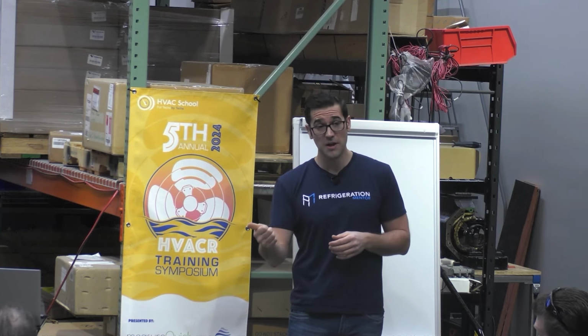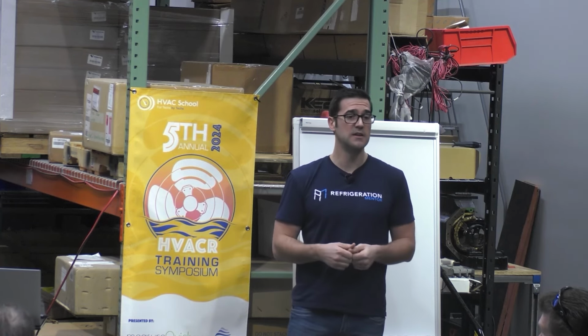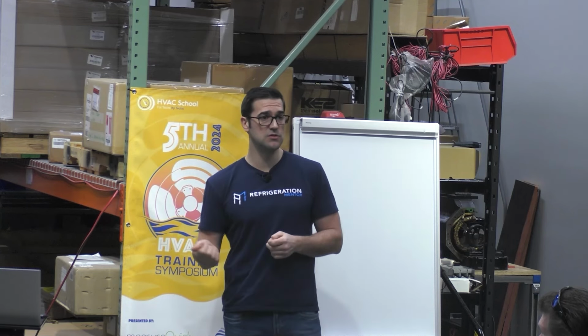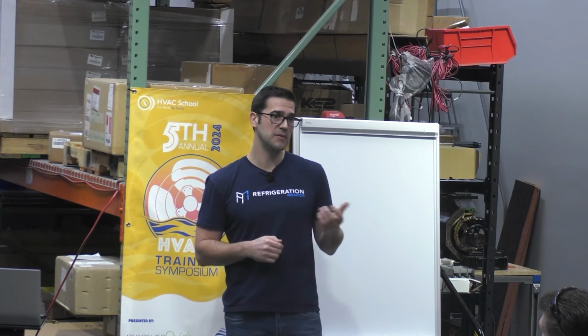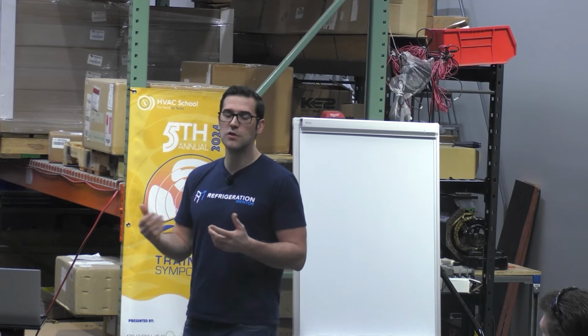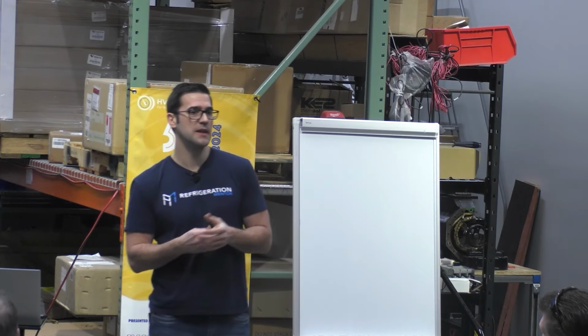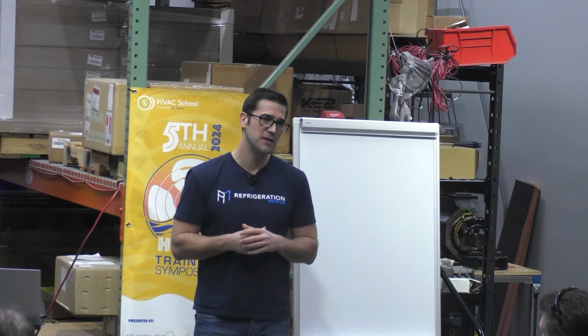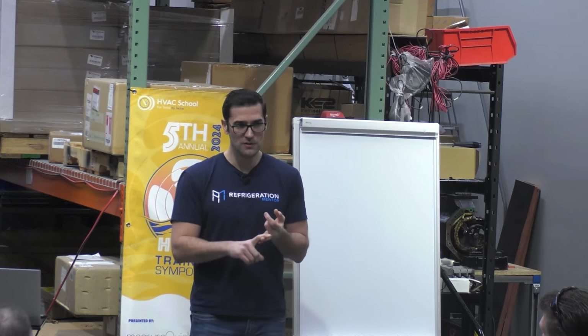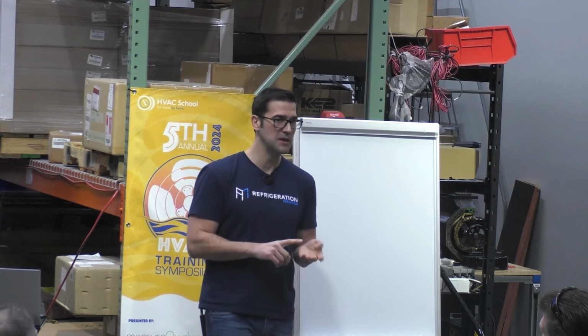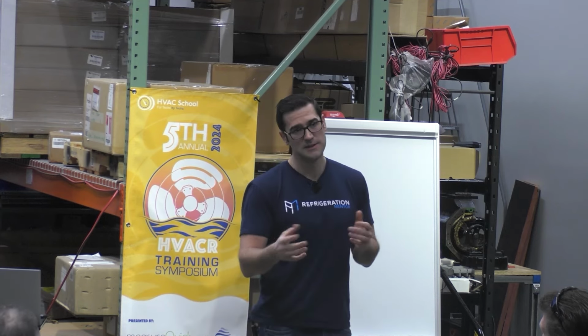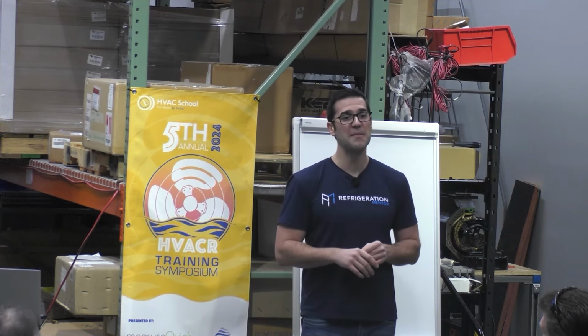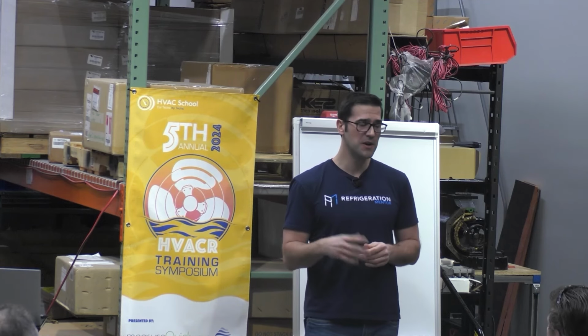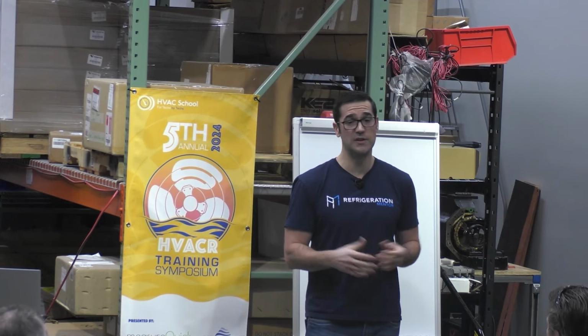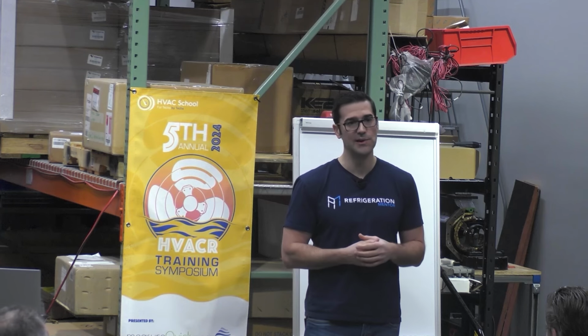With CO2, you get smaller pipes. You get smaller compressors. You get more capacity from a CO2 compressor than from an HFC compressor at the same size. So these are just the things that you need to learn about over time. But on energy efficiency, I've seen so many different models. Do you have heat reclaim? Are you using air conditioning with it? Is it medium or low temp? What's the design? It's hard to do an apples to apples comparison. But at some point, I believe it'll be more efficient, and it's regulations that are pushing it as well.